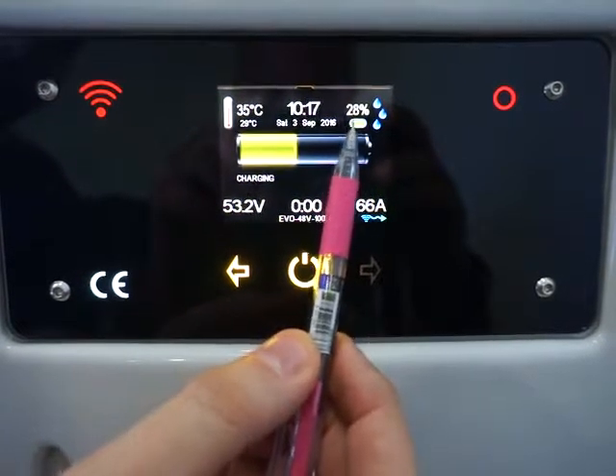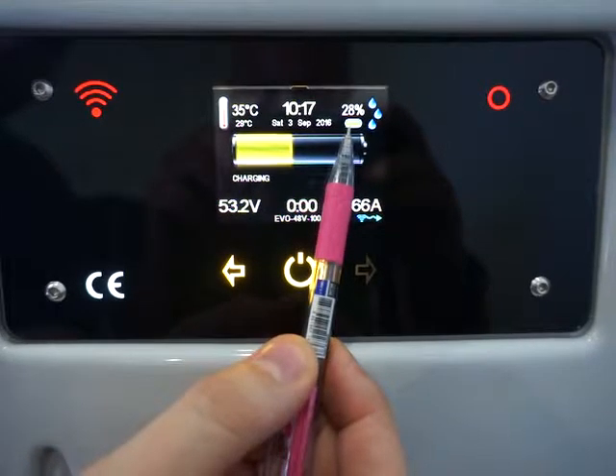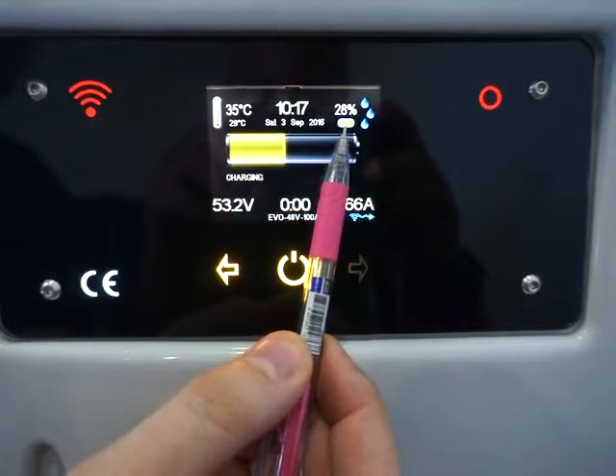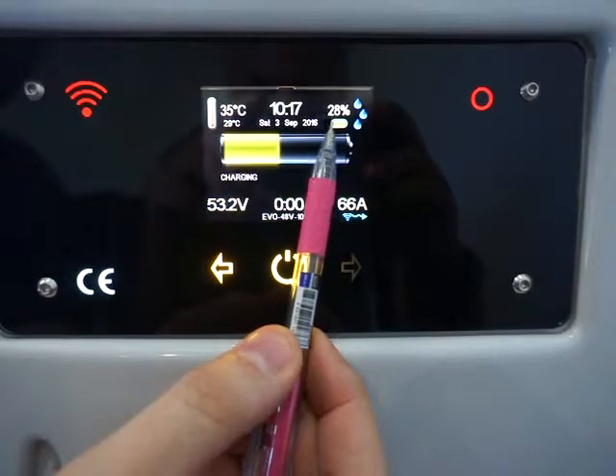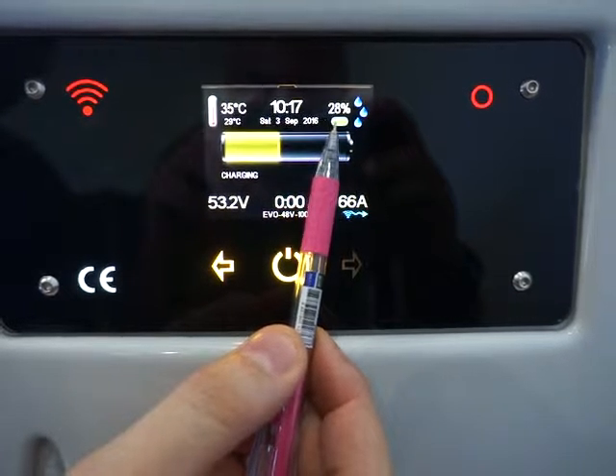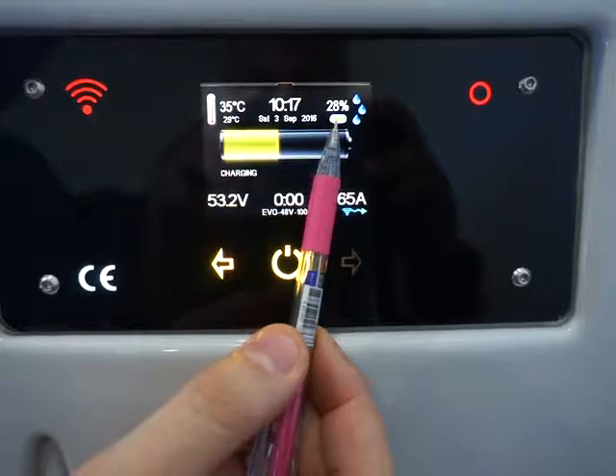Now I will remove the water level sensor from the other battery, the 48 volt 100 amp, and show you that if the water level is too low, the charger will not start and will give a warning error.